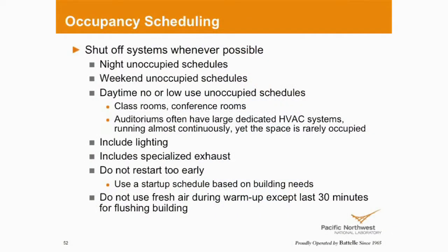I'm going to say, you know what? If I started at 6 a.m., I may not recover. If I start at 5 a.m., I may not recover. We've seen some sites go as early as midnight. So they're shutting off at 6 p.m. and they're starting back up at midnight because that's their operating experience. I'll never recover if I don't start early. And that might be true for certain outdoor conditions. So optimal start is a learning program, and it has some benefits.